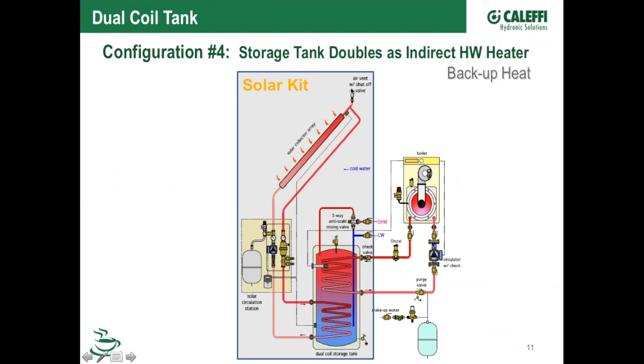You've got a couple of different options, but it definitely helps you when you fill it up and when you first fire it up because until the sun starts heating up that fluid, you don't get all the air driven out. And it's really hard to de-aerate glycol. I don't know if you've ever experienced that, but it's a lot tougher to get the air bubbles out of glycol than plain fluid. So it can take a little bit longer. It can take a couple days until that collector gets up to a high operating temperature that you've got all that air evacuated out of it.